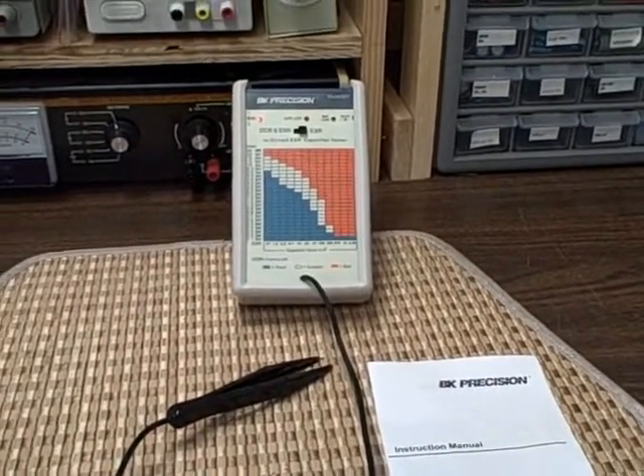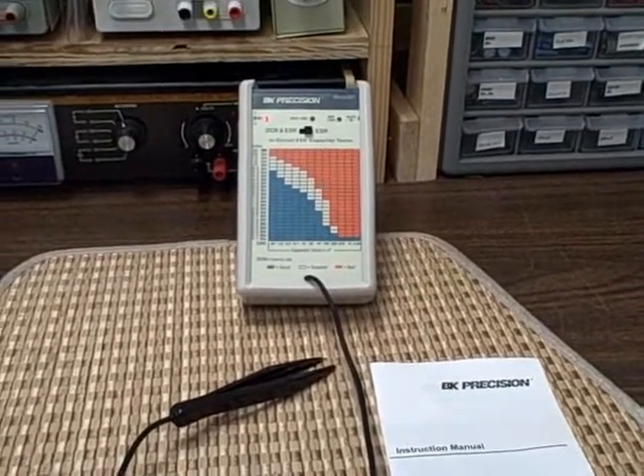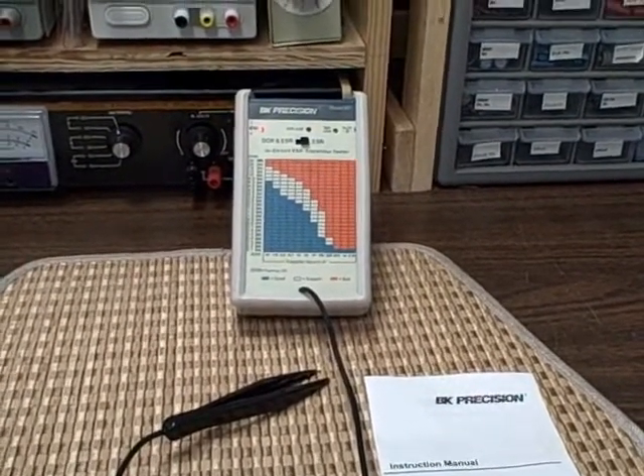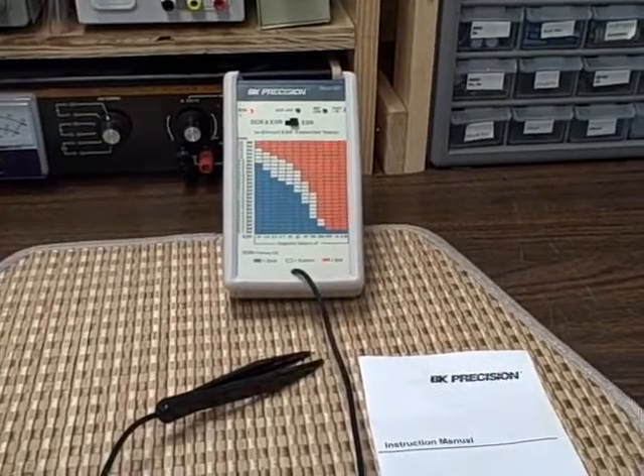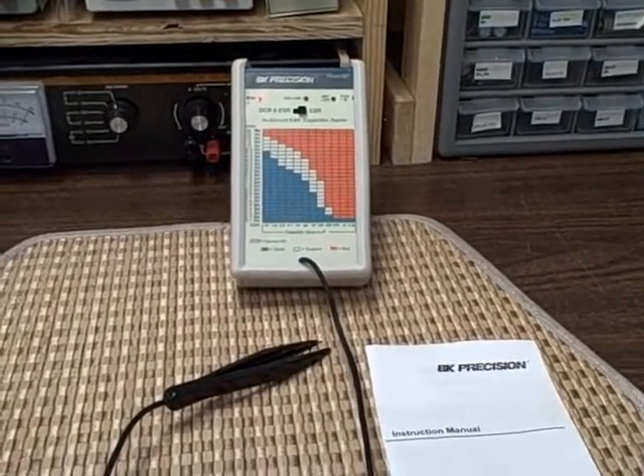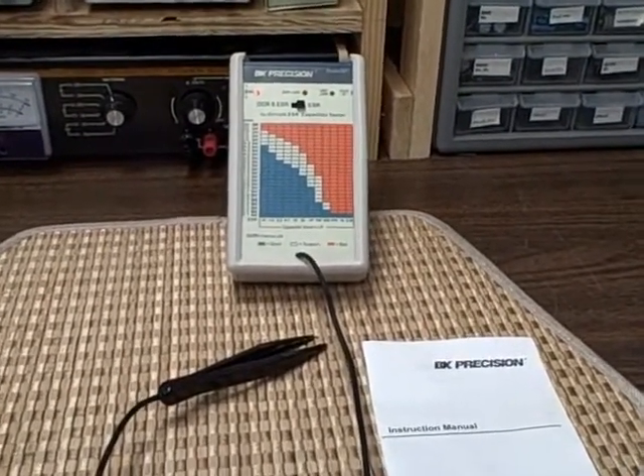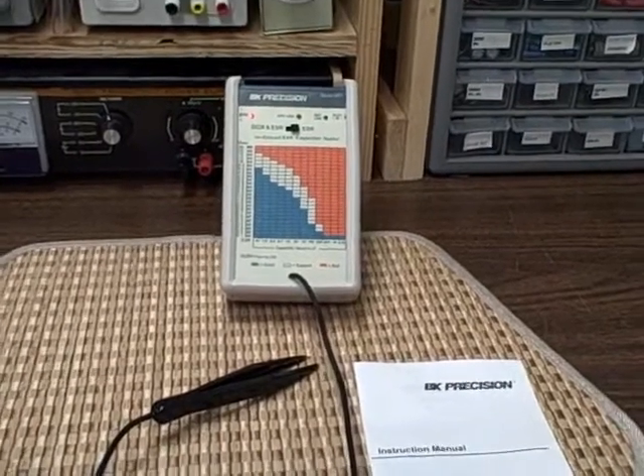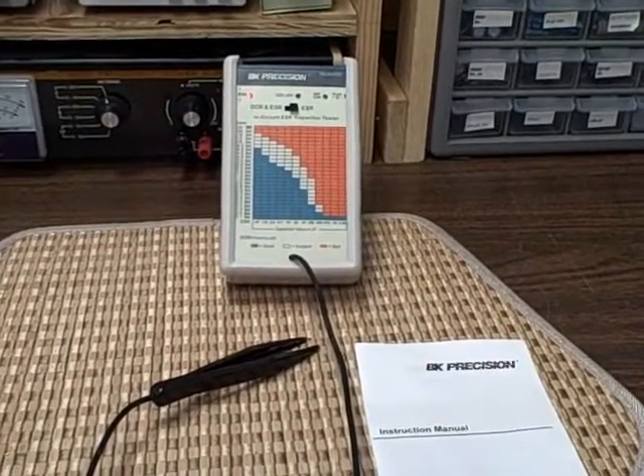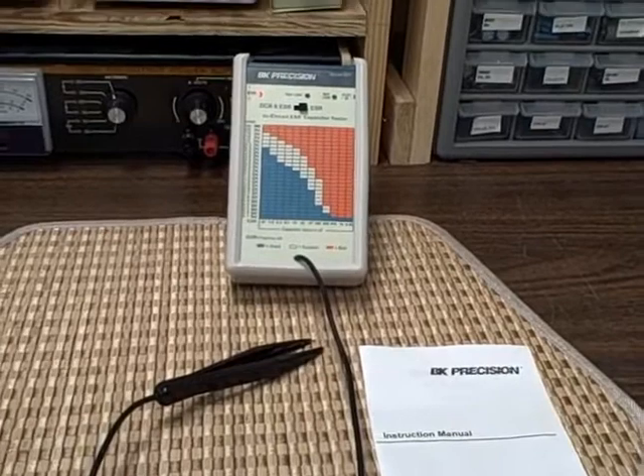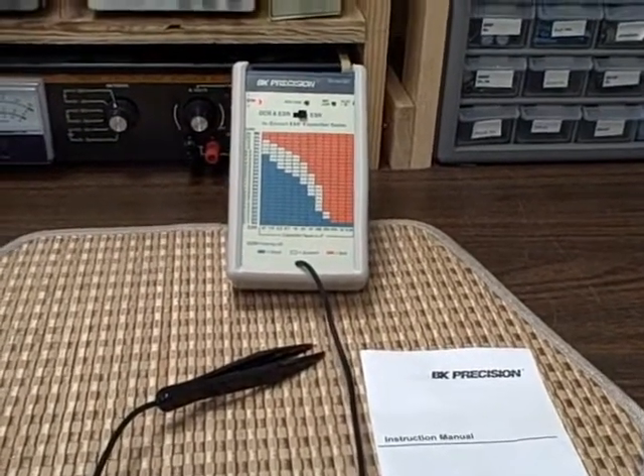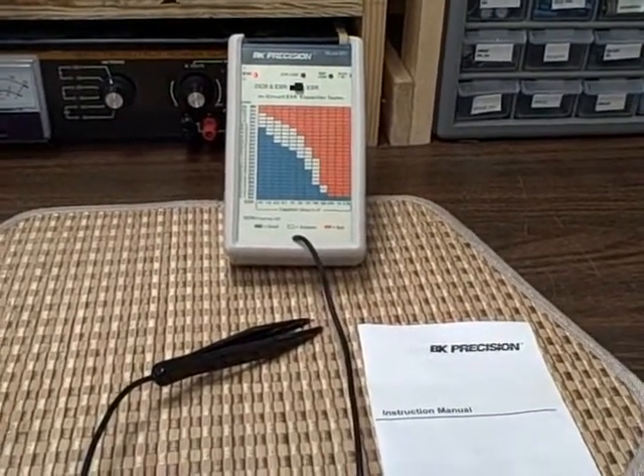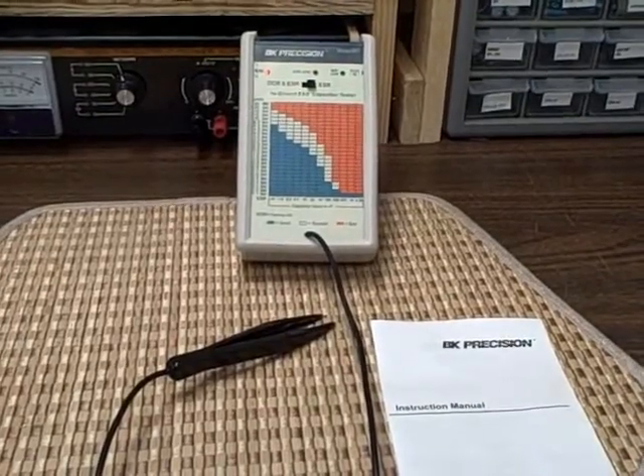What this unit does is it allows you to test either in or out of circuit the DC resistance and then the equivalent series resistance of capacitors in the range of about 0.47 to about 2200 microfarads. These are the most significant problem sources, particularly in power supplies.